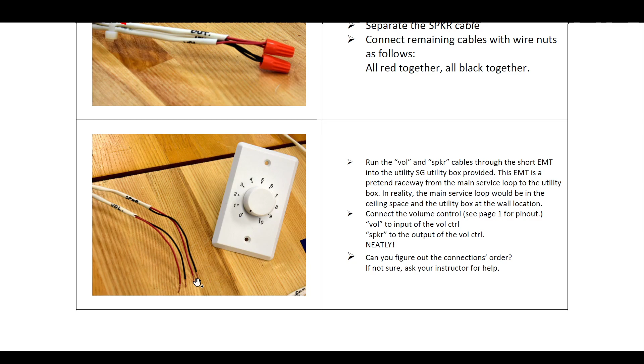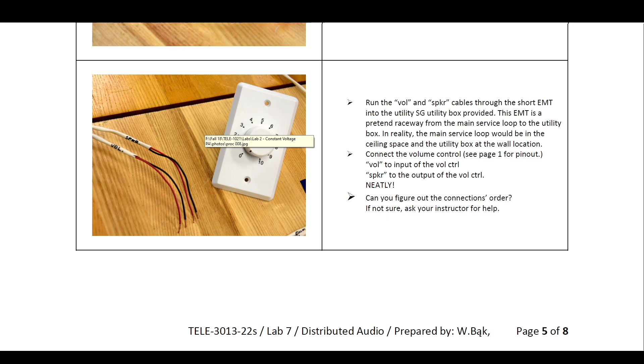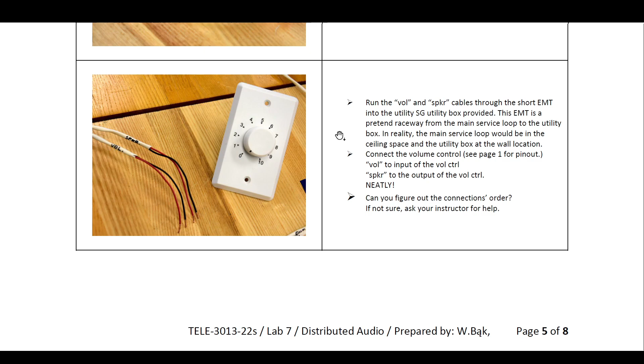Here is the volume control. One thing I want to point out: when you strip the wires, notice the stripped lengths over here — those lengths are equal. Maybe the jacketings aren't equalized to the millimeter, but when you tie them together with a zip tie, the ends physically should be the same length so you don't make a mess. All installations should be done neatly. Neatness is a lifesaver when doing big jobs with many connections. If you don't develop a sense of neatness, you'll run into trouble figuring out what you did two days earlier. You'll make that mistake once, and from then on you'll start developing more neatness with every job. I just want you to be aware of that.